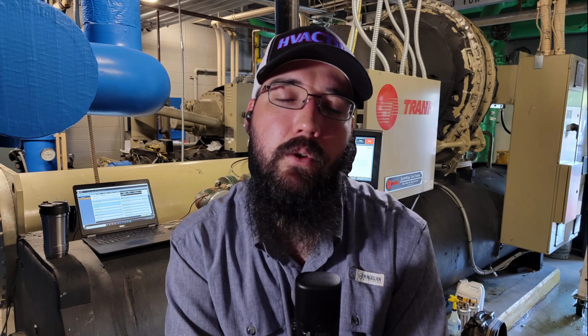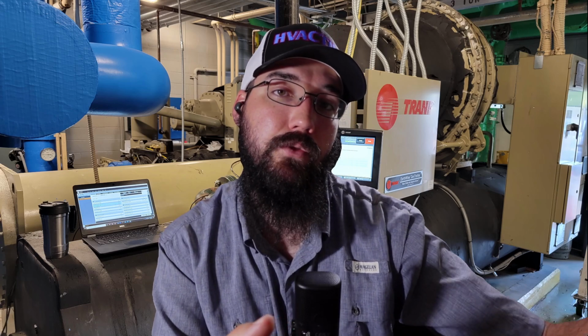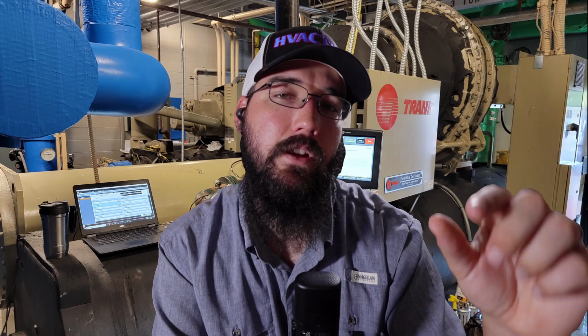So going from fully closed to open, if everything worked right, there should always be a little bit of a stop for just a moment, even if it's just a couple of seconds, where you feel and you can hear that valve hit the top end. And when that doesn't happen, and you can see in the plunger or through the sight glass that the plunger didn't move, in many cases it will move to the point where you may not even be able to see it in the top of the sight glass anymore. Like it's out of visible range. Or you may just barely see the very bottom tip of it.